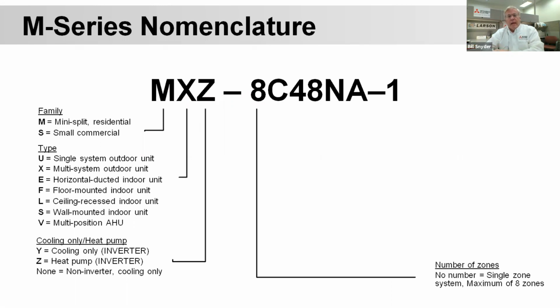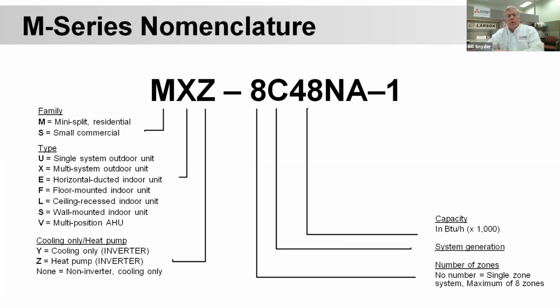So this particular MXZ 8 would indicate that it was 8 zones. The next C there is just a generational change. It was an MXZ 8B prior to this. Now it's an 8C. And that next 48 would indicate simply 48,000 BTUs or a 4-ton, figuring a nominal 12,000 BTUs per ton. So that would be a nominal 4-ton unit. The next digits, NA, the N would mean it's 208, 230. All of the equipment we're going to talk about today is 208, 230, with the exception of one model with two versions of that model, which will be 115 volts that I'll cover in a few minutes.